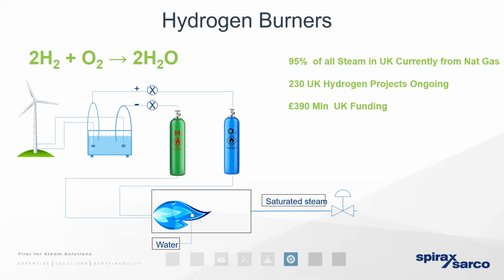And as far as steam's concerned, well, we know that hydrogen's clean burning. Basically, when we burn hydrogen and oxygen together, the byproduct is water vapor. So there's no harmful emissions, and therefore there's no carbon dioxide, carbon monoxide, any other source of gases to give thought to as a result of that combustion byproduct. So hydrogen and steam have got a very, very good fit because hydrogen could potentially be distributed in the same natural gas infrastructure. I say potentially because at the moment there's some debate whether or not hydrogen is suitable for being distributed in the traditional cast iron pipe work compared to the more modern yellow MDPE pipe work. So that puts a question mark over the distribution network itself.